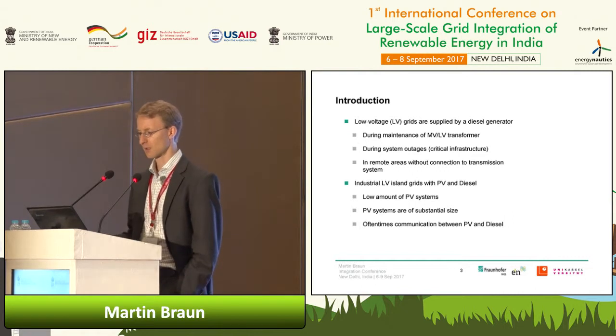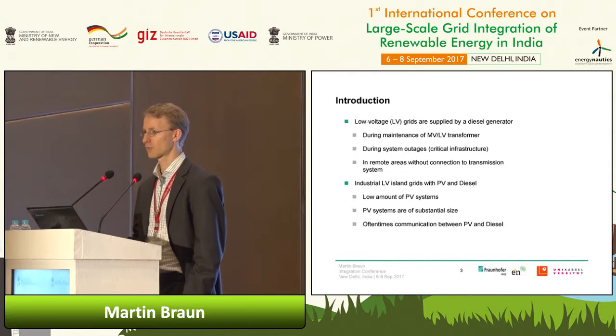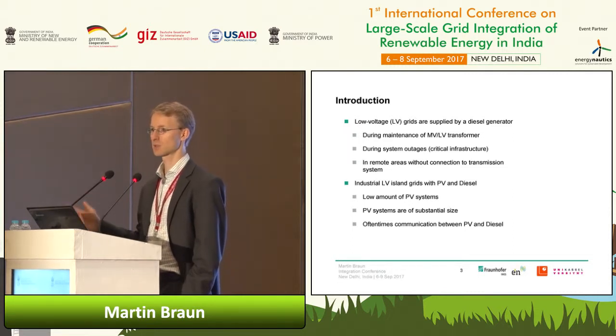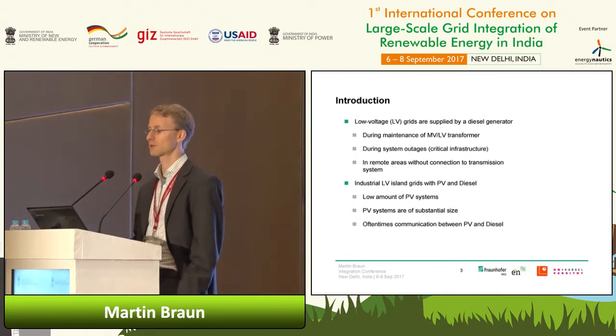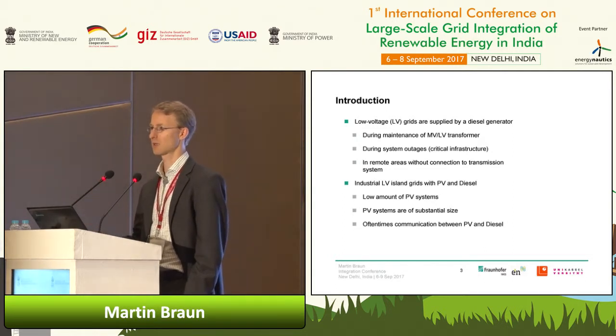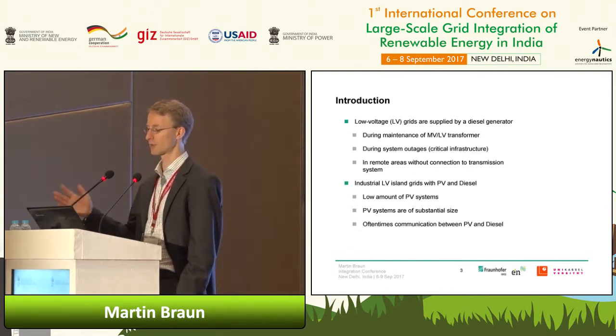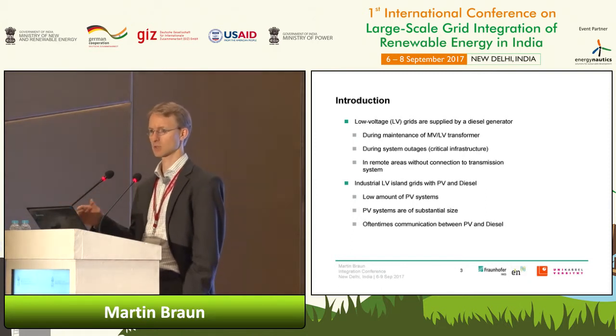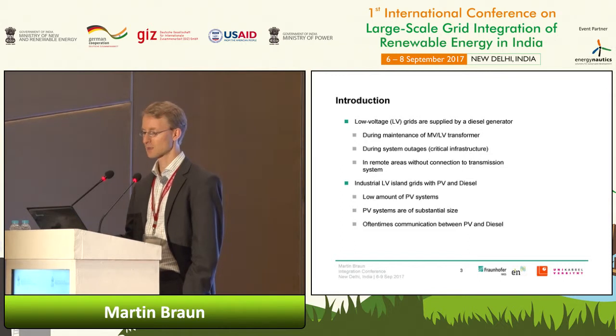So first, we normally don't really have diesel gensets in the German context anymore, as we have a very reliable grid. Diesel gensets are more for emergency units at customer sites, but grid operators also use diesel gensets when they have to maintain or repair anything in the low voltage areas. They disconnect from the medium voltage, low voltage transformer, apply the emergency genset, and just operate further, even in a maintenance situation. It can also be imagined, or rather it is not just imagined, that during outages diesel gensets are allocated to critical infrastructure. This is mainly, for example, substations, to get power for network restoration. So they are applied there.